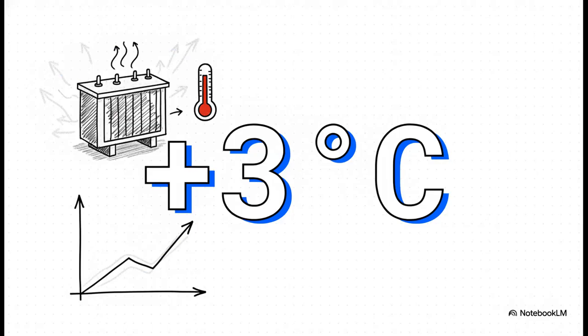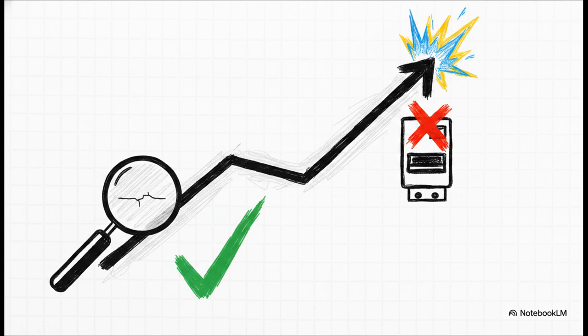Let's put this into perspective with a real-world scenario. Say you've got a 2000 kVA unit, and its hotspot is trending at 98 degrees Celsius against a strict 105-degree limit. At first glance, 98 degrees is under the limit. You're probably thinking, hey, everything's totally fine. But actually, if that number steadily climbs 3 degrees a month and your electrical load hasn't changed at all, you have a serious problem brewing. The absolute number might technically be fine, but that upward trend line, it's literally screaming at you that something inside the tank is generating abnormal heat.